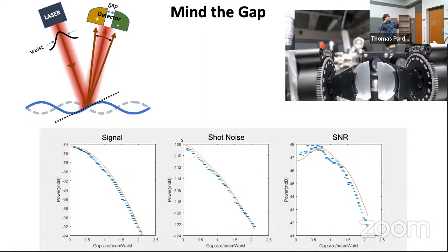And so to answer a simpler question, to get not just a better quantum efficiency but overall better measurement strength, you want to make a Gaussian beam that's as big as possible, meaning that it encompasses almost an entire acoustic wavelength. Then you're actually getting light where your device is moving. The obvious way of saying that is that if your spot size on your device is bigger, the divergence angle of your beam is smaller. And what you're doing is comparing that divergence angle to the actual deflection angle. Then your signal to noise goes up for a lower numerical aperture beam.